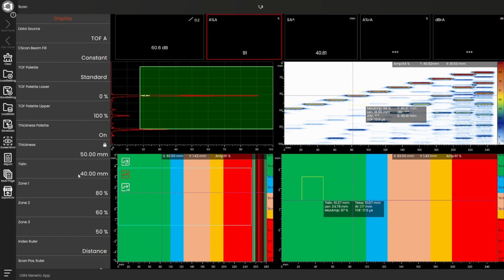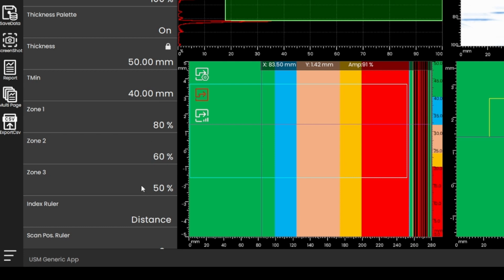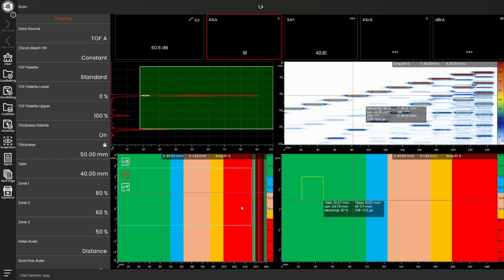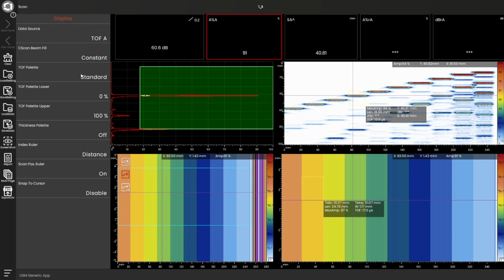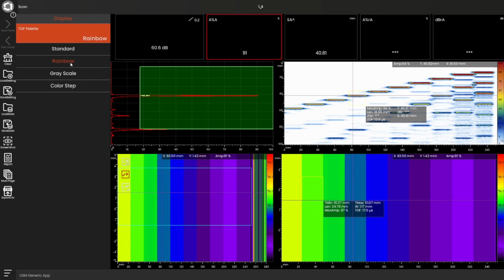But we've said our nominal thickness is 50 millimeters. The minimum thickness that we want to consider as good is 40 millimeters. And then we have several bands of increasingly bad below that. So we say anything between 80% of 40 millimeters and 100% is going to be blue. Anything between 60 and 80 is orange or taupe color. Anything between 50 and 60 is yellow, caution. And below 50% of minimum thickness, we want to see red. All right, so this is a very useful feature if you're doing corrosion scanning. The step block is maybe not the most interesting piece of corrosion data, but this gives you the idea of how the new thickness palette is intended to work. So thickness palette's either on or off. Other than that, you have the standard amplitude and time of flight palettes to choose from.